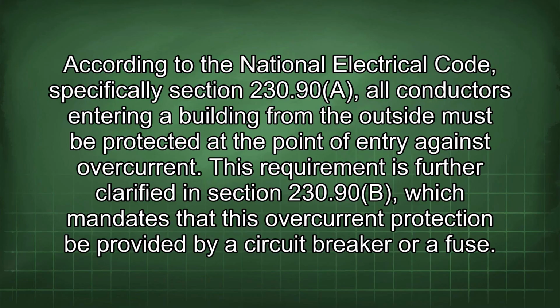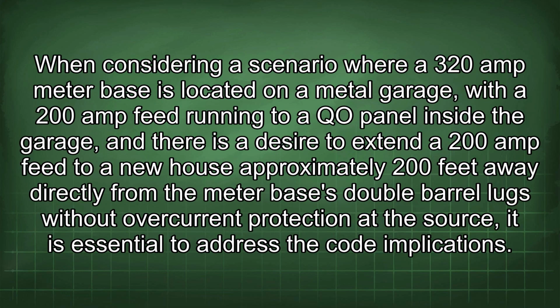According to the National Electrical Code, specifically Section 230.90(A), all conductors entering a building from the outside must be protected at the point of entry against overcurrent. This requirement is further clarified in Section 230.90(B), which mandates that this overcurrent protection be provided by a circuit breaker or a fuse.